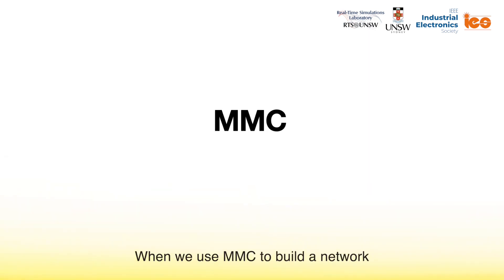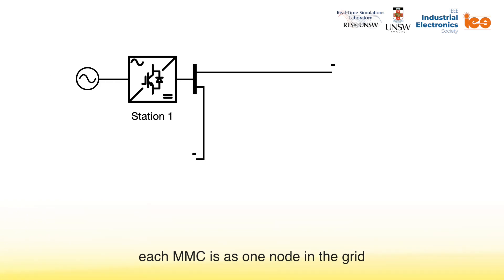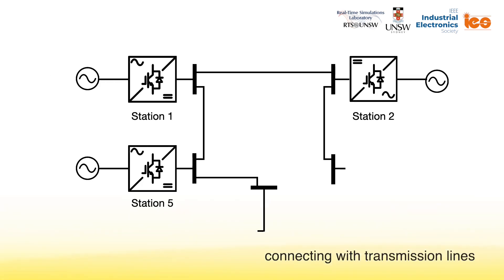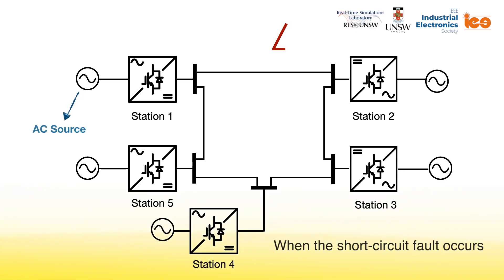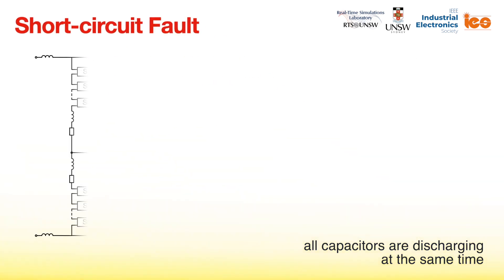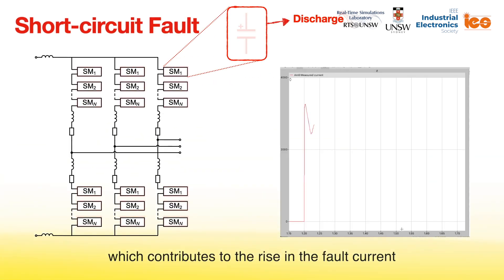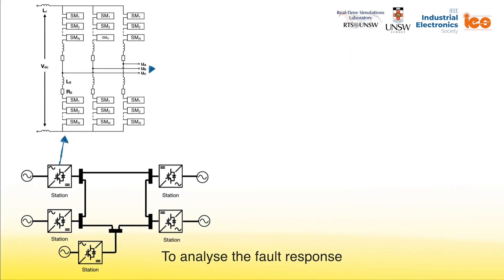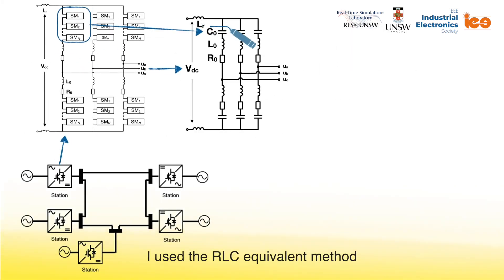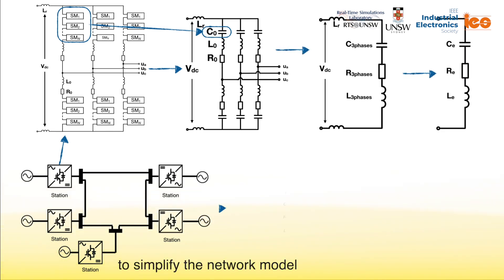When we use MMC to build a network, each MMC acts as one node in the grid, connecting with transmission lines or cables that are like branches in this network. When a short-circuit fault occurs, all capacitors are discharging at the same time, which contributes to the rise in the fault current. To analyze the fault response and calculate the fault current, I used the RLC equivalent method to simplify the network model.